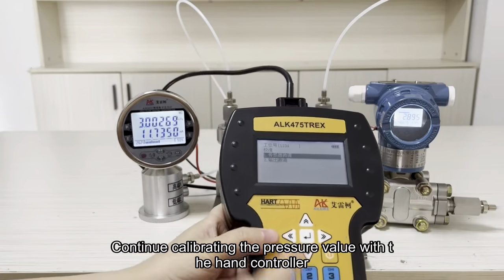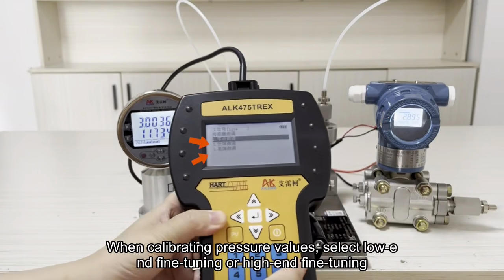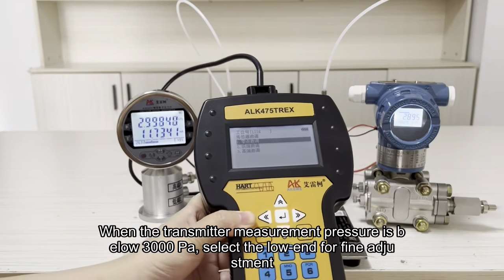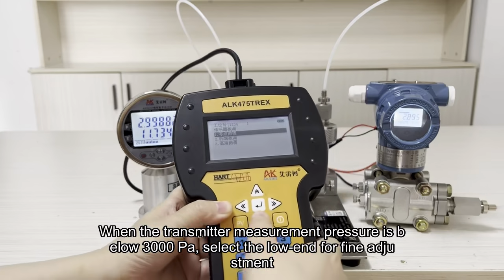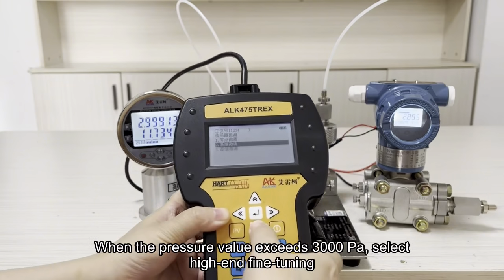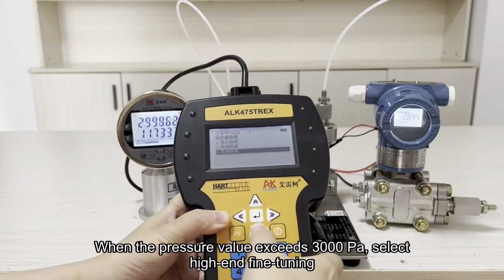Continue calibrating the pressure value with the hand controller. When calibrating pressure values, select low-end fine-tuning or high-end fine-tuning. When the transmitter measured pressure is below 3000 Pa, select low-end fine-tuning. When the pressure value exceeds 3000 Pa, select high-end fine-tuning.